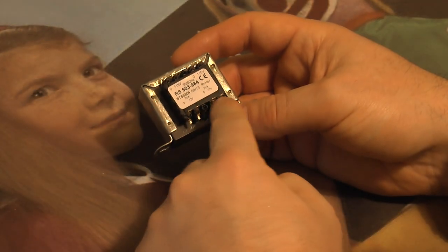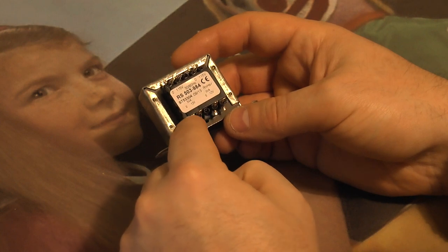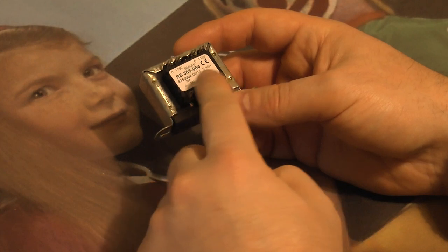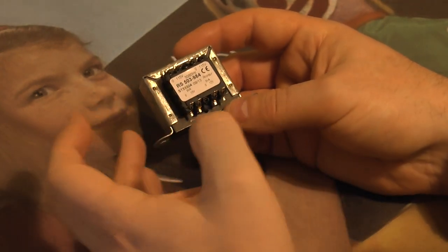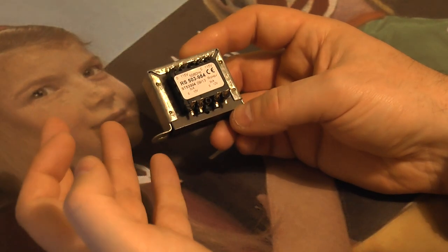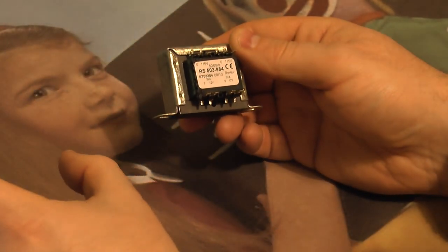These are only 3VA transformers so they were cheap enough anyway. Now I mentioned that I'm not using most of the low voltage windings on these transformers, so I'm going to centre tap these to the transformer cases. So the highest voltage present on those windings relative to the case in this instance is 12 volts. I'm also going to connect the centre tap of the high voltage windings to the case. Not that I need to, but in some transformer applications you might find that that connection is already there and you've got no choice. So I'm just attempting to prove that such a connection shouldn't be a problem as long as the transformers are insulated from each other.